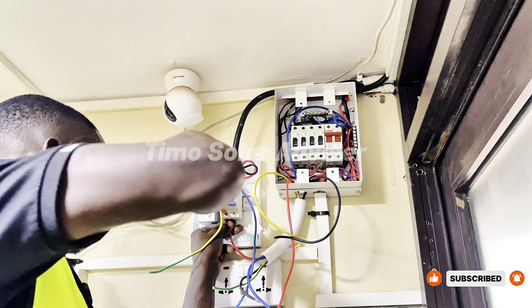I told you, remember, your breaker has to be every time switched down so that you don't get any unexpected short circuit in any connection when you are connecting. So I want to first put these cables a bit. So on the left, this is the supply to the inverter. So this is the supply from the inverter. Still, it is going to go in the main switch so that we are going to do the isolation of our loads, which have to be connected to the inverter. Okay, so this one is going to go straight. It has to pass through here. So it means we don't need any breaker here because these breakers are going to be controlling the output from the inverter straight to the breakers, which are going to supply the loads.